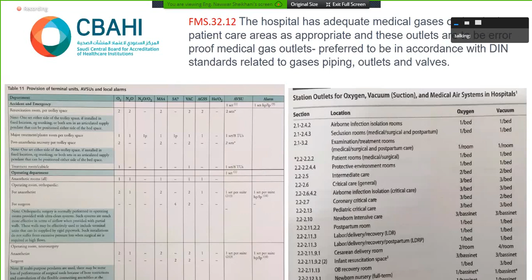32.12, hospital has adequate medical gas outlets. Here we have 2 references. Please choose one of them. The right side is mentioned in the facility guidelines, which is related to ASHRAE, I think, and the left side is related to HTM, as mentioned. Both are acceptable, but usually in CBAHI we recommend HTM. Okay, we are done with medical gas.